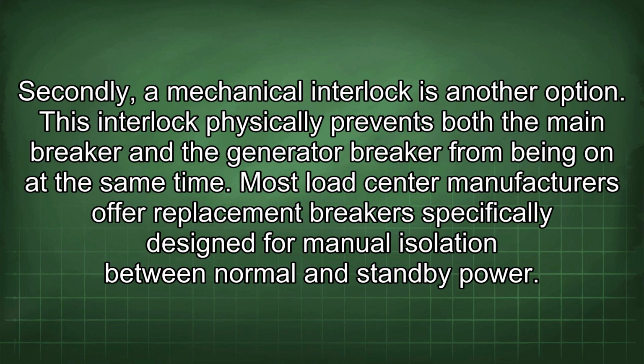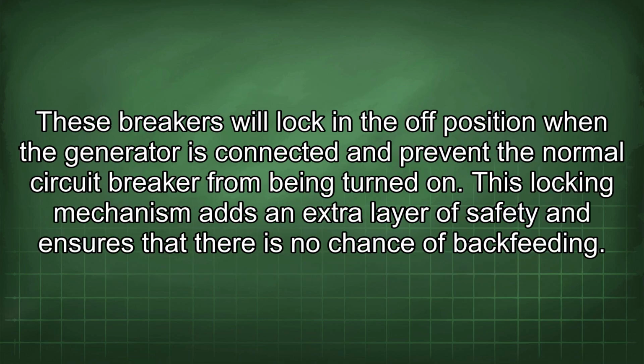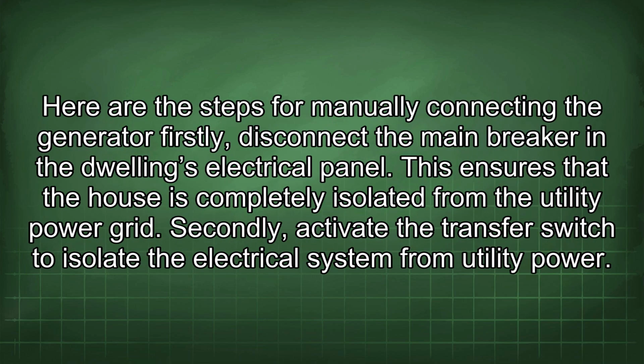Most load center manufacturers offer replacement breakers specifically designed for manual isolation between normal and standby power. These breakers will lock in the off position when the generator is connected and prevent the normal circuit breaker from being turned on. This locking mechanism adds an extra layer of safety and ensures that there is no chance of backfeeding. Here are the steps for manually connecting the generator.